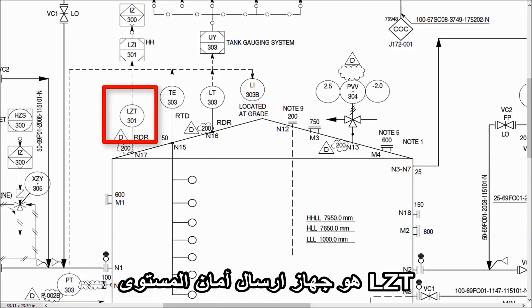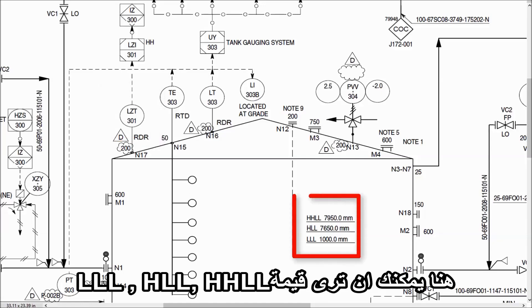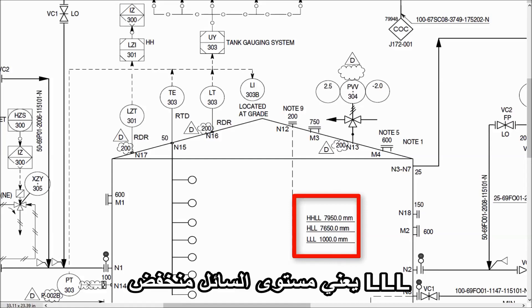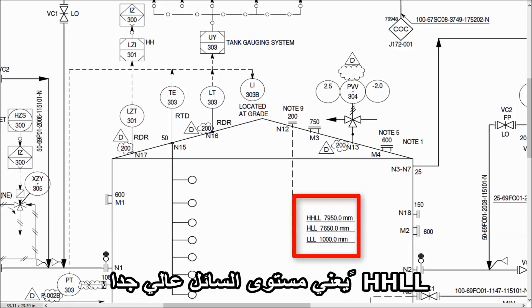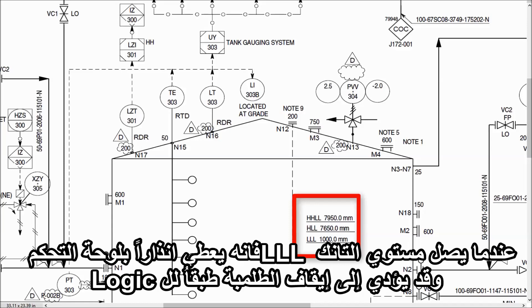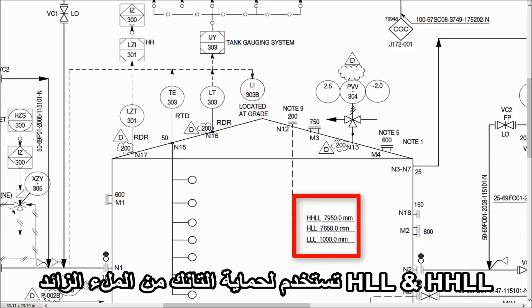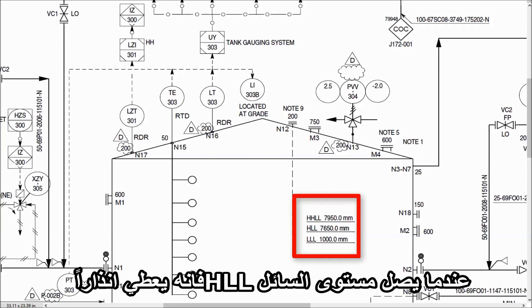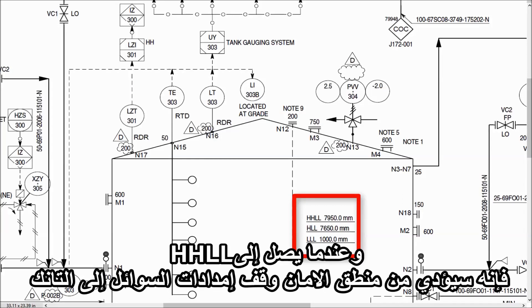LZT is a level safety transmitter. Here you can see the values of LLL, HLL, and HHLL. LLL means low liquid level, HLL means high liquid level, and HHLL means high high liquid level. LLL protects your pump — when the tank level reaches LLL, it gives an alarm on the control panel and, based on the logic configuration, may trigger a switch-off command to the pump. HLL and HHLL are used to protect the tank from overfilling. When the liquid level reaches HLL, it gives an alarm, and when it reaches HHLL, it triggers the safety logic and stops the fluid supply to the tank.